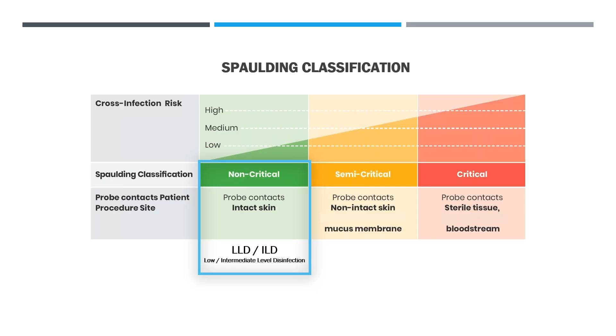And so we assign a level of risk, and based on that, we can then assign what level of disinfection. So for non-critical studies, intermediate or low-level disinfection is appropriate, and for either semi-critical or critical, high-level disinfection is required for the probes. The disinfectants used, first of all, a disinfectant that is used on a medical device needs to be of an instrument grade, and these are regulated by the TGA or Therapeutic Goods Administration. There's low-level, intermediate level, and high-level disinfection dependent on the range of organisms that they kill.